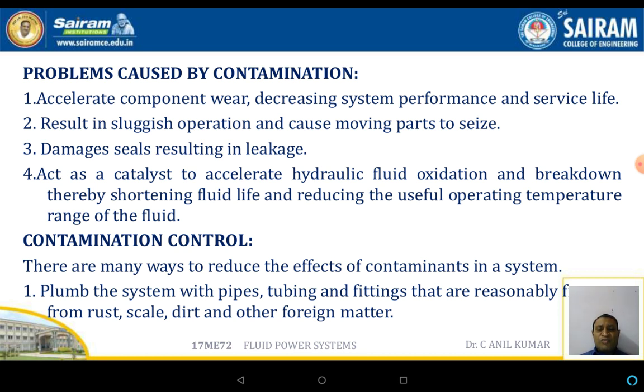If metallic or oxidized particles start flowing in the oil, there is a chance of seizing. The third problem is damaging seals, resulting in leakage. The fourth problem is acting as a catalyst to accelerate hydraulic fluid oxidation and breakdown, thereby shortening fluid life and reducing the useful operating temperature range. As contamination increases in the hydraulic system, viscosity starts increasing.